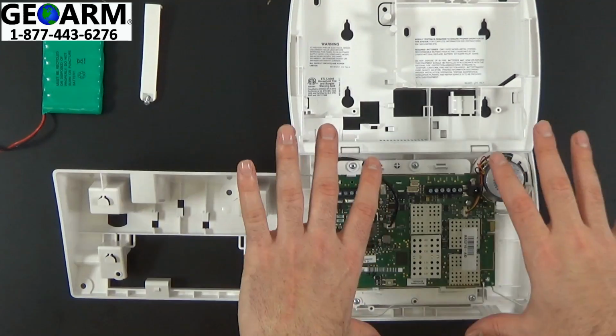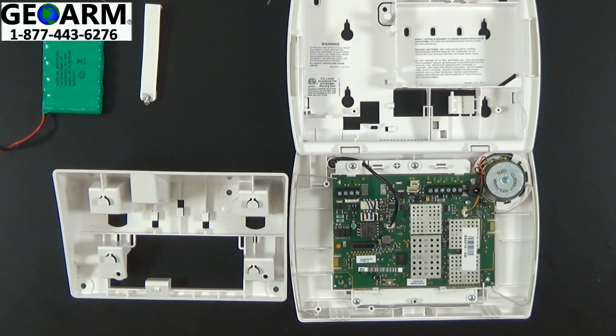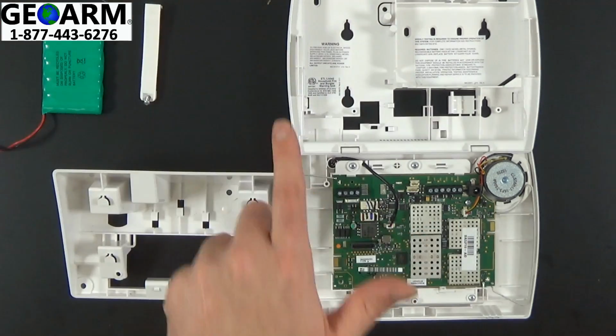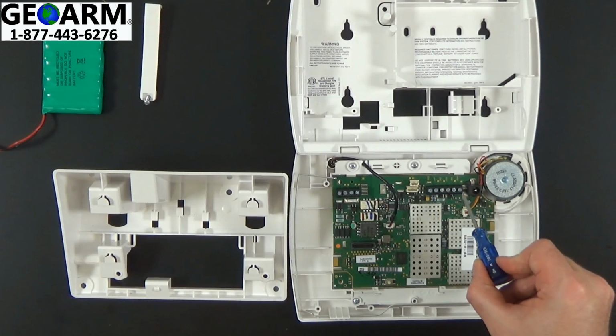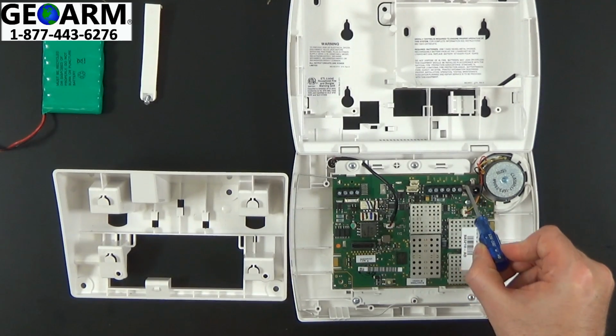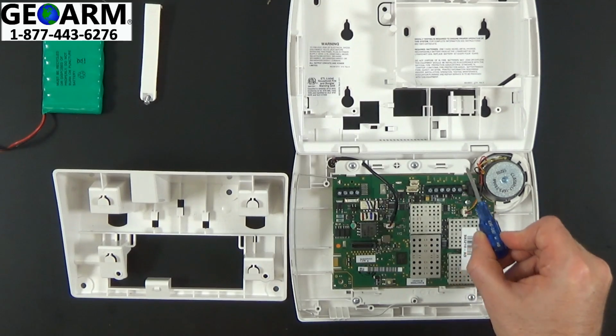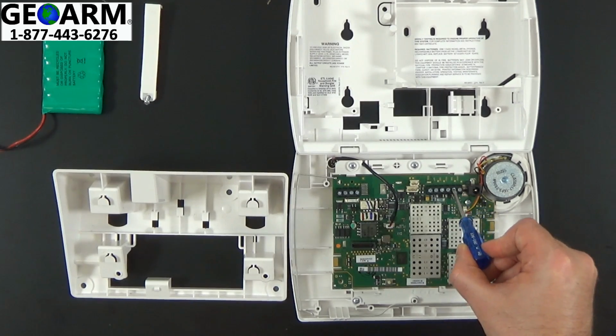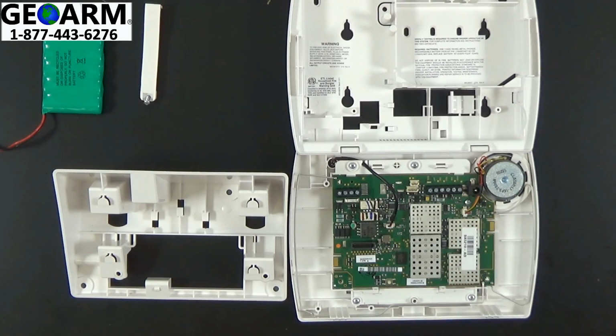This exposes the inside of the 5210 panel. Briefly, if you didn't have the LT cable, you'd still wire the red wire into the positive and the black wire into the negative on the transformer, then run it through the back of the panel to the 9 VDC terminal, where the red wire is power and the black wire goes to GND, which is ground. Today we have the LT cable, so I'll show you how to install it, which is much easier.